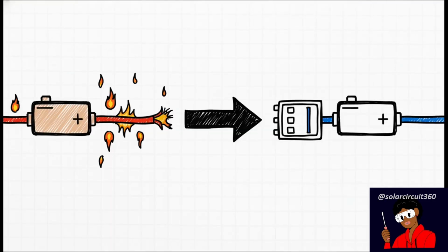But hey, the danger isn't only inside the inverter box itself. Using undersized cables gives you bad voltage drop, crazy heat buildup, and eventually the insulation literally melts off the wire. But you want to know the absolute biggest hazard of them all? Missing fuses. Listen to me. The inverter alone does not, I repeat, does not provide adequate fault protection for your system. A properly rated fuse has to be installed physically as close to that battery source as you can manage. Without it, you're risking uncontrolled fault current and catastrophic fires.